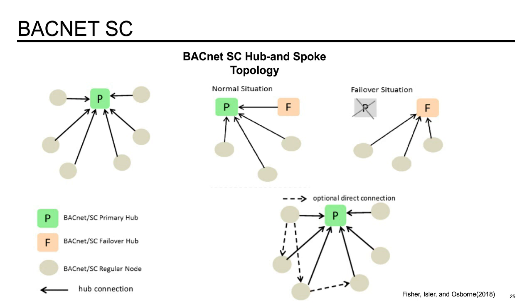BACnet devices on a BACnet SC network must use the same primary hub, but the devices can use a different failover hub. And then regular nodes can perform direct connection to other regular nodes in addition to going through a hub. So let's take a second and just look at the pictures here. On the left-hand side, we see an installation with a primary hub and then the BACnet SC nodes connecting to the primary hub. Then in the middle top, we see a situation with the failover hub. And on the right-hand side at the top, if the primary hub fails, then the device is moved to the failover hub. And then you also have the capability with BACnet SC devices to allow direct connect to other SC devices on the primary network that the hub serves. I want to point out the primary hub is required. The failover hub is an optional device that's not required in all installations.